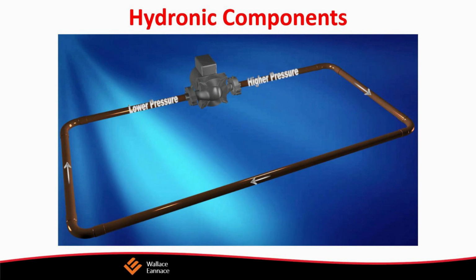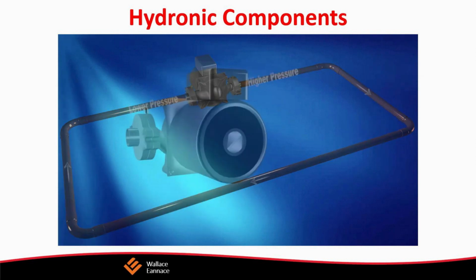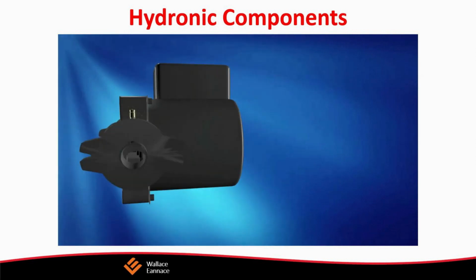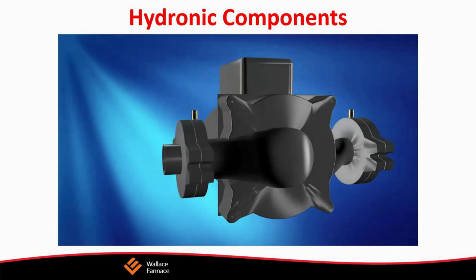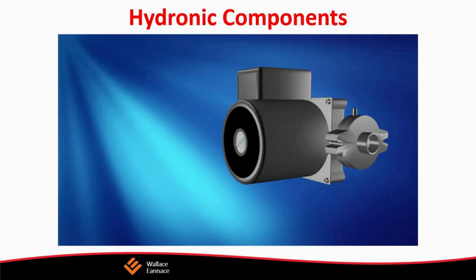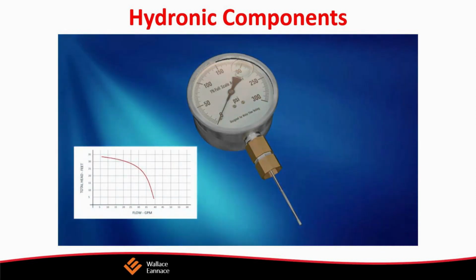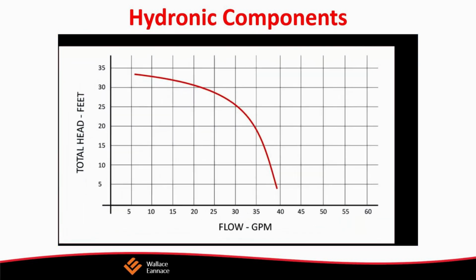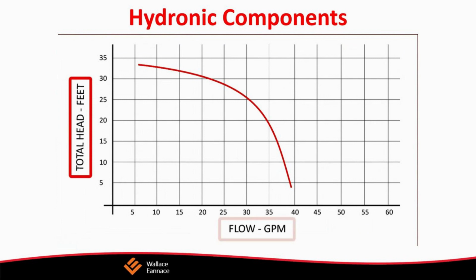The impeller is the part of the circulator that spins, slinging water away and creating the delta P, or difference in pressure, when the motor is energized. The motor is the electrical device that is connected to the impeller by a shaft and is responsible for turning the impeller. It's good that we know the anatomy of a circulator when we try to understand how they work. This image represents a circulator in a closed system.